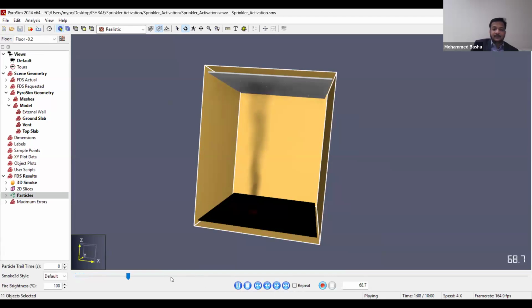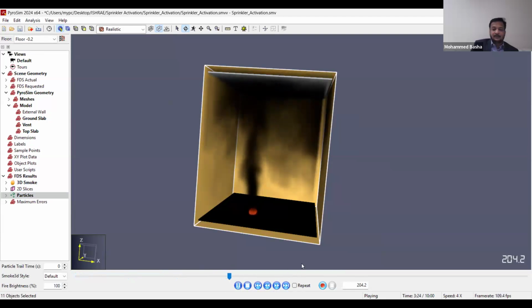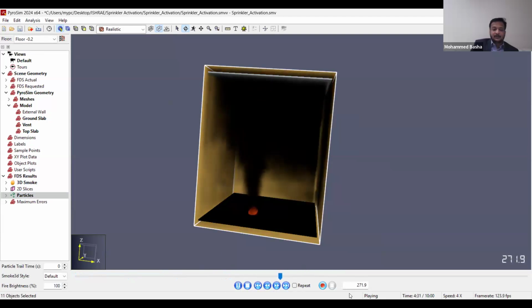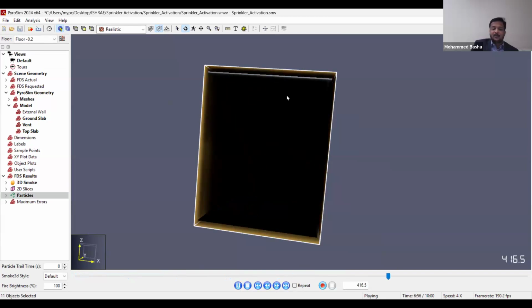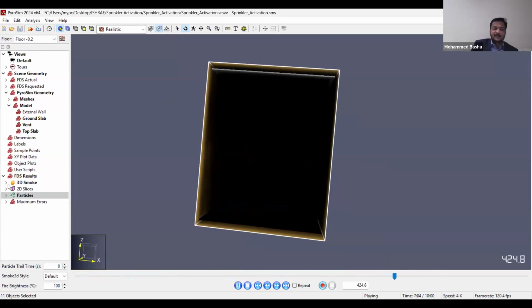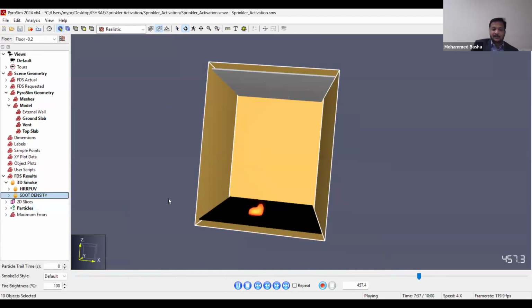The fire grows. But surprisingly, in this simulation, none of the sprinklers are getting activated till the smoke completely comes down and makes a disaster for the occupants there. So what is the purpose of having a smoke management system if I allow the smoke to completely come down? See, the fire is burning. It's a medium growth fire. Since the ceiling is very high, it cannot take the fire.